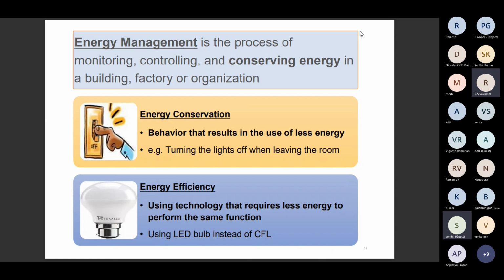Whereas in energy efficiency, without switching off the lights, the existing fluorescent tube lights can be replaced with energy efficient LED lamps, so we get the same lux level and lighting level and maintain our comfort, but still achieve nearly 50% energy saving, because a 40 watt tube light can be replaced with a 20 watt LED lamp. In both activities we save energy. The difference is that energy conservation is behavior where our comfort level is reduced to save some energy, whereas energy efficiency uses the latest technology to achieve the same function and performance with less energy. Next one.